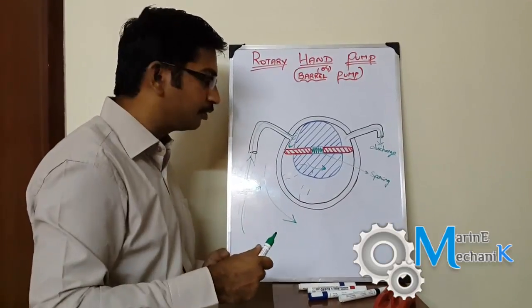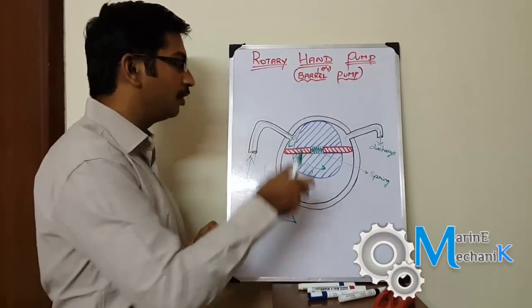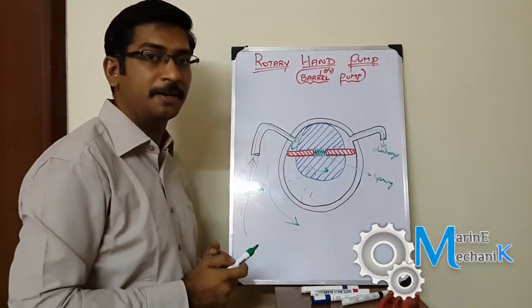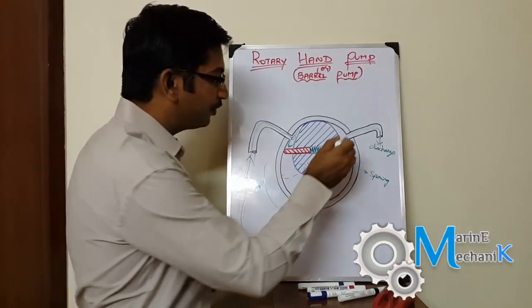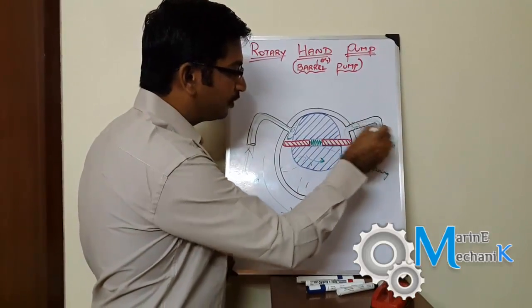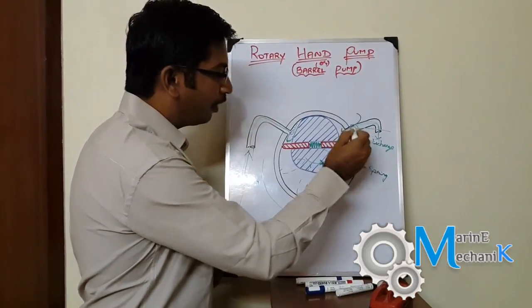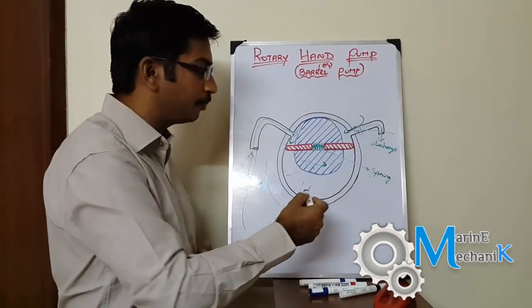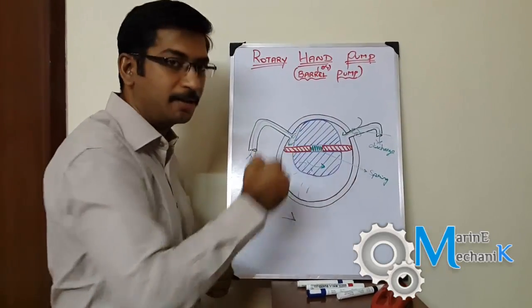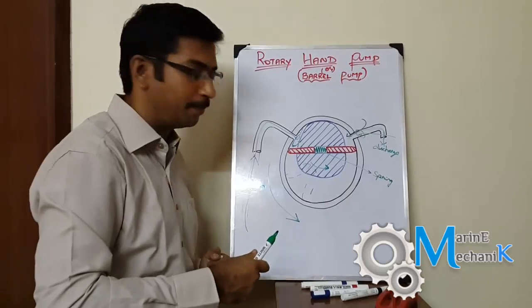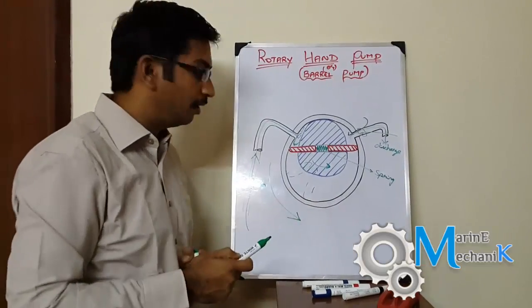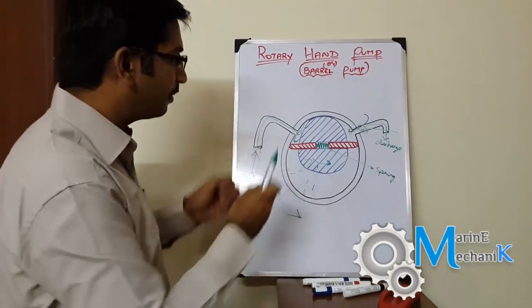So it is not able to pump out air enough, which means it is not self-priming. In that scenario, what you need to do is just remove this connection and pour some oil or water, whichever you are going to pump, to prime this area completely and then start pumping. This will work.